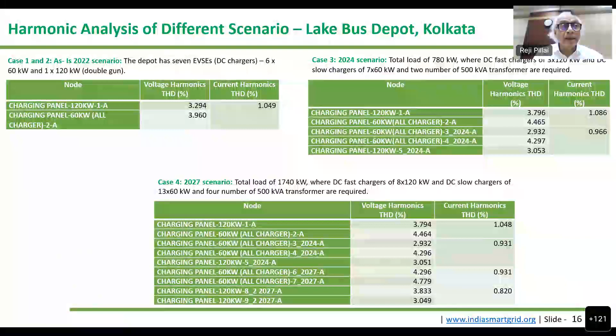So the key findings from the whole study are that the load flow study results of the 2022 scenarios and the PQM measurements have been compared and found to be in alignment. The scenarios studied for 2024 and 2027 assumed additional EVSE loads besides the normal load growth, and found voltage sags and harmonics beyond acceptable limits in those scenarios. The EVSE load growth assumed for 2024 and 2027 could not be verified by the relevant stakeholders, so we did not actually estimate mitigation measures for harmonics in that scenario.